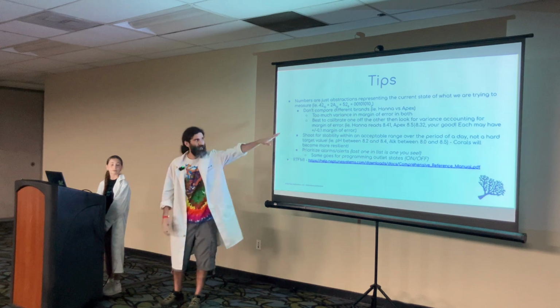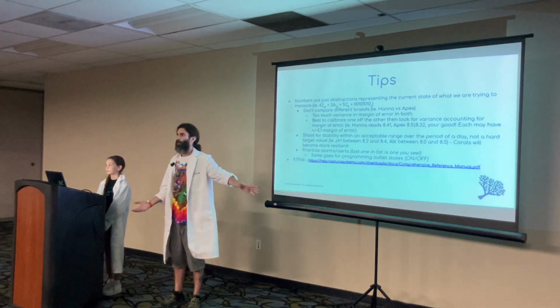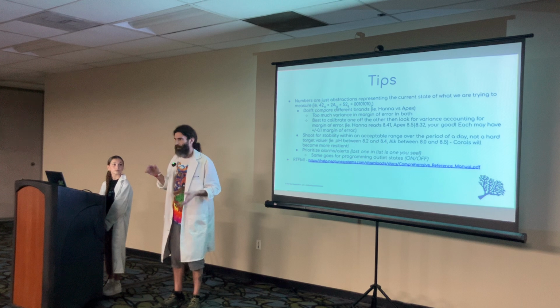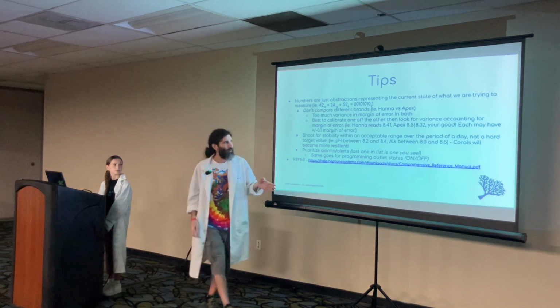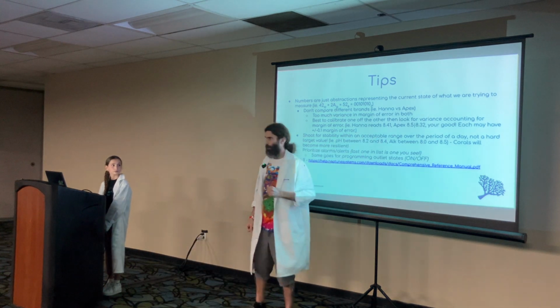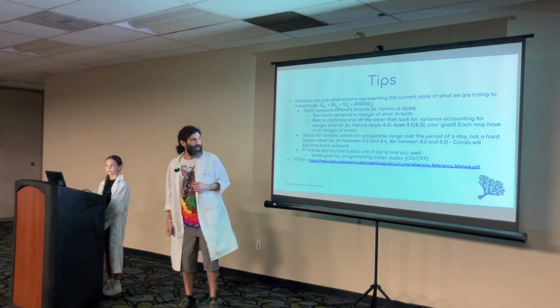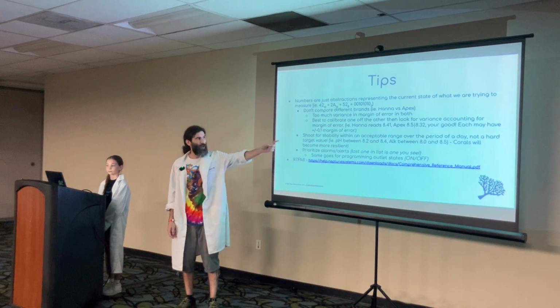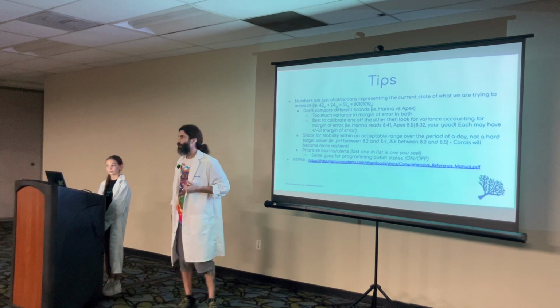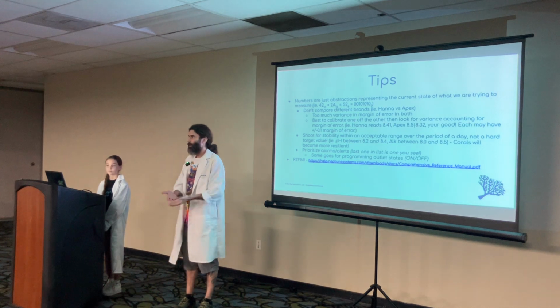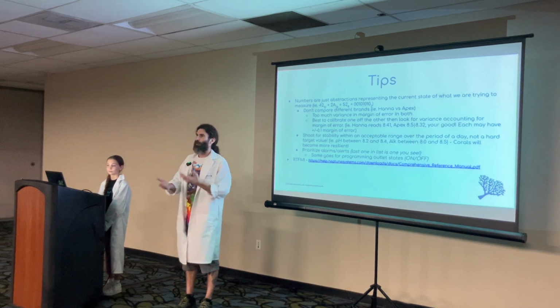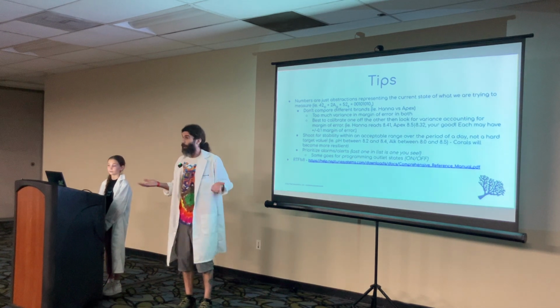So all these things have a margin of error. It could be 0.1 on either side, 0.2 on either side, 0.01, whatever. You have to remember that your Hanna and your Apex both have a margin of error. So if your Hanna is reading 8.41, right, and your Apex is reading either 8.5 or 8.32, they're probably good. They're probably reading the same value. It's just you're dealing with a margin of error. And those can swing even a little bit more and still be the same.